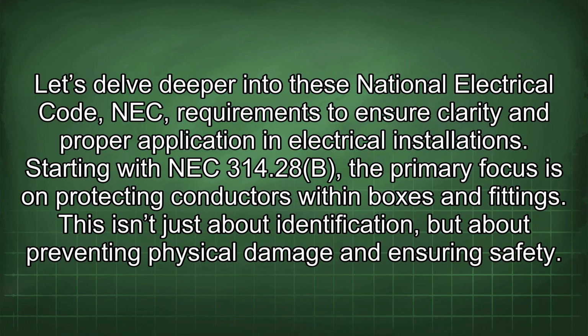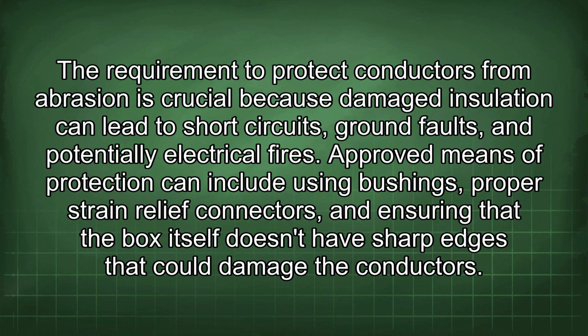Starting with NEC 314.28(B), the primary focus is on protecting conductors within boxes and fittings. This isn't just about identification, but about preventing physical damage and ensuring safety. The requirement to protect conductors from abrasion is crucial because damaged insulation can lead to short circuits, ground faults, and potentially electrical fires. Approved means of protection can include using bushings, proper strain relief connectors, and ensuring that the box itself doesn't have sharp edges that could damage the conductors.